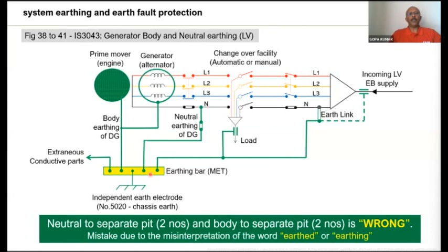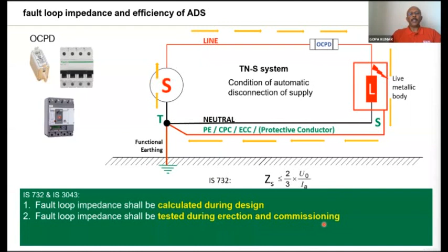If we don't follow the fault loop impedance, or if we don't test it, technically speaking, the standards, the codes of practice IS 732 and IS 3043, recommend calculating the fault loop impedance during the design, testing it during erection and commissioning, and periodically checking it for safe disconnection. The periodicity is also there. For example, regulation 30 part 1 says every 5 years.